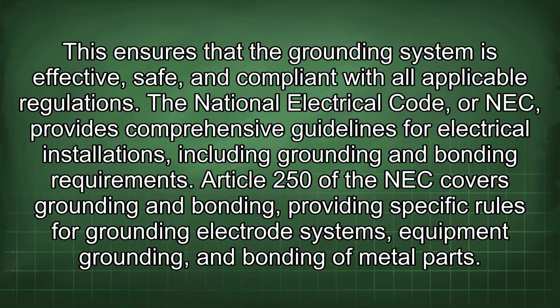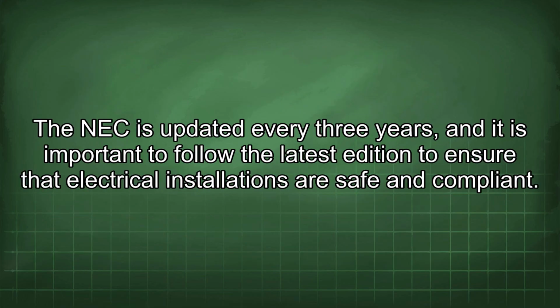The National Electrical Code, or NEC, provides comprehensive guidelines for electrical installations, including grounding and bonding requirements. Article 250 of the NEC covers grounding and bonding, providing specific rules for grounding electrode systems, equipment grounding, and bonding of metal parts. The NEC is updated every 3 years, and it is important to follow the latest edition to ensure that electrical installations are safe and compliant.